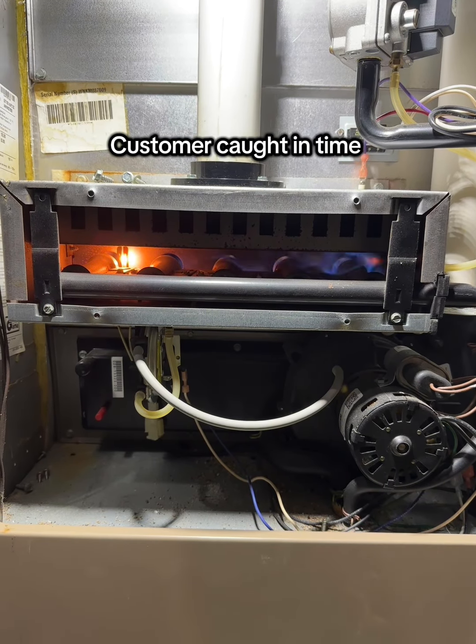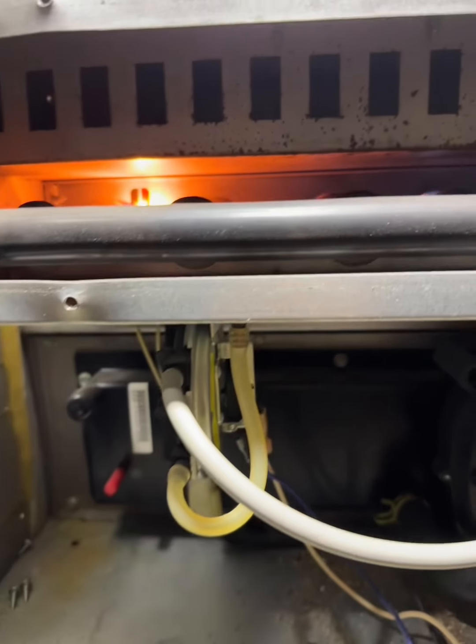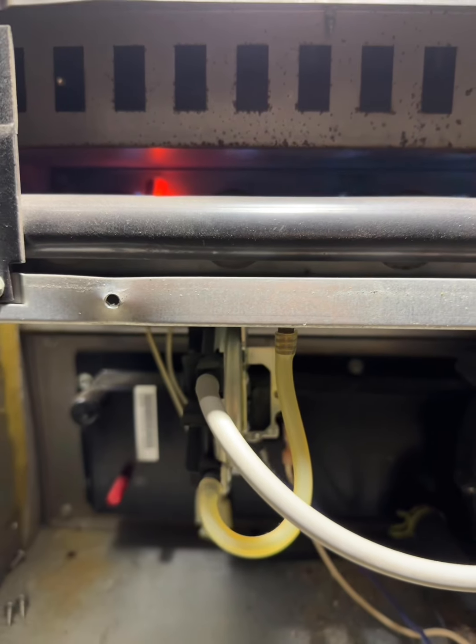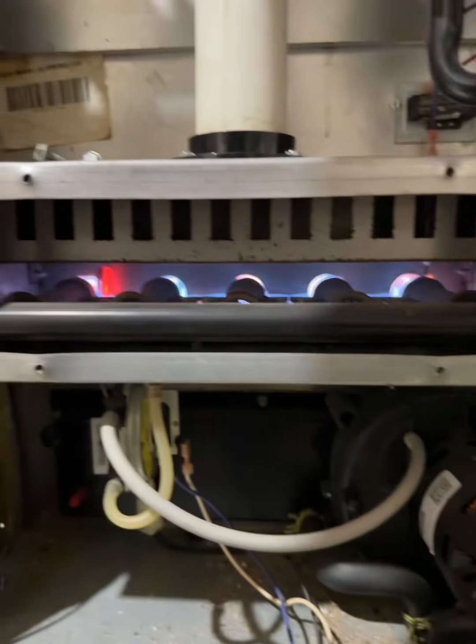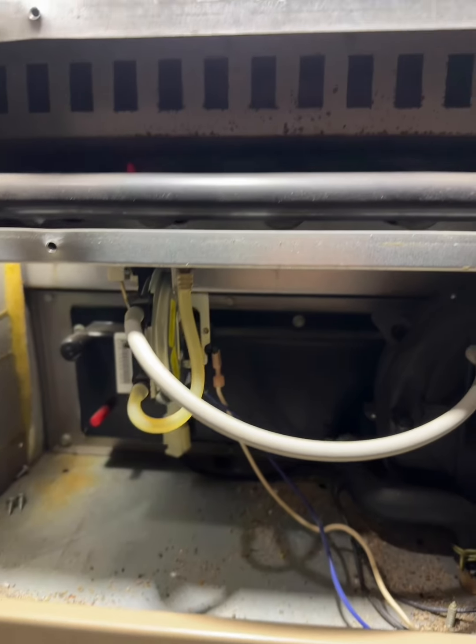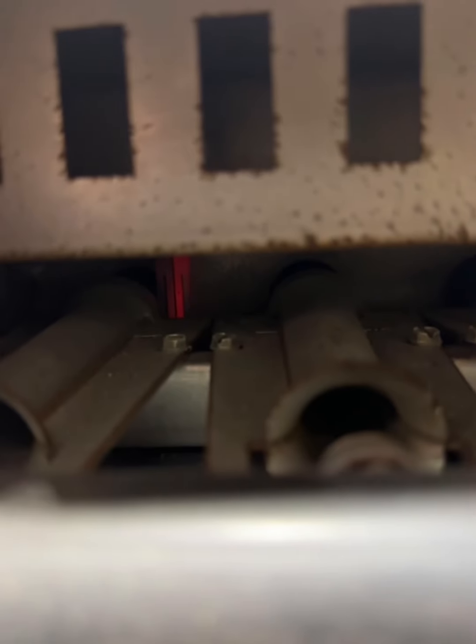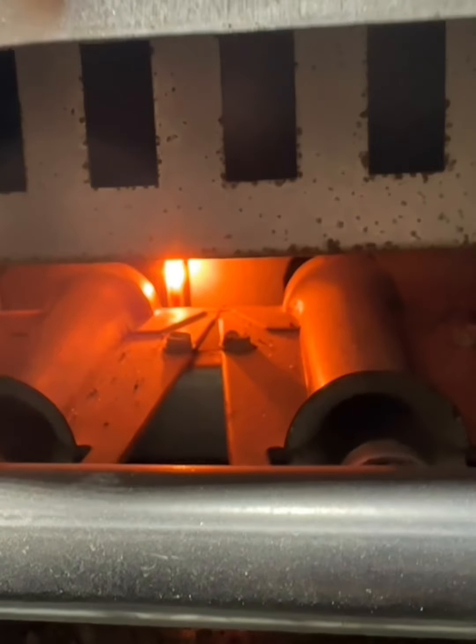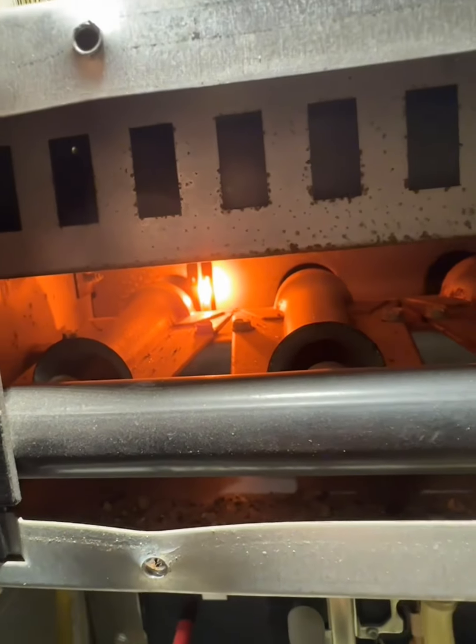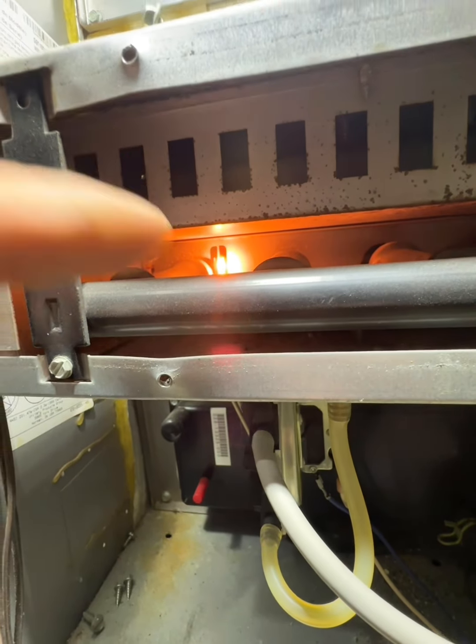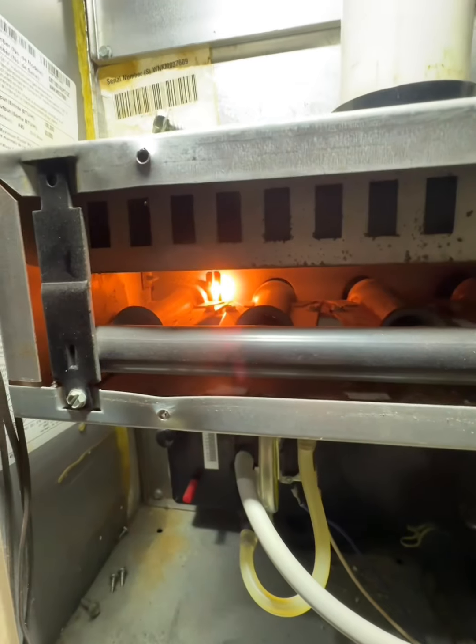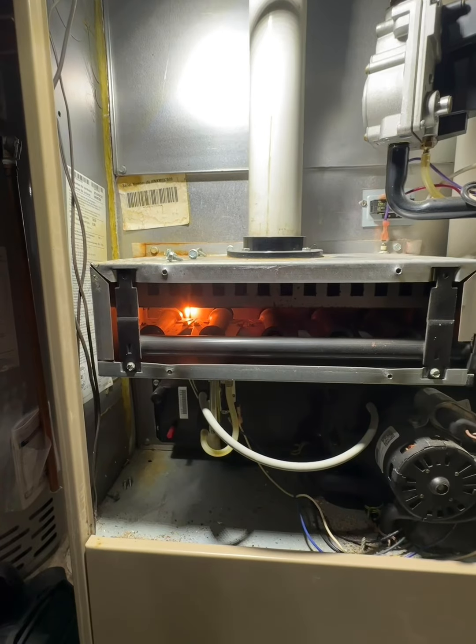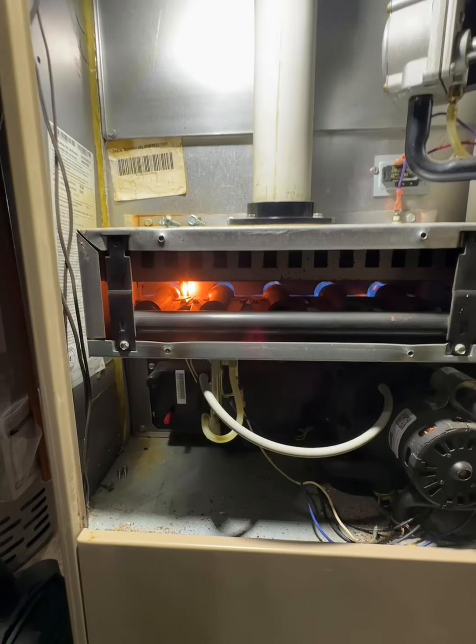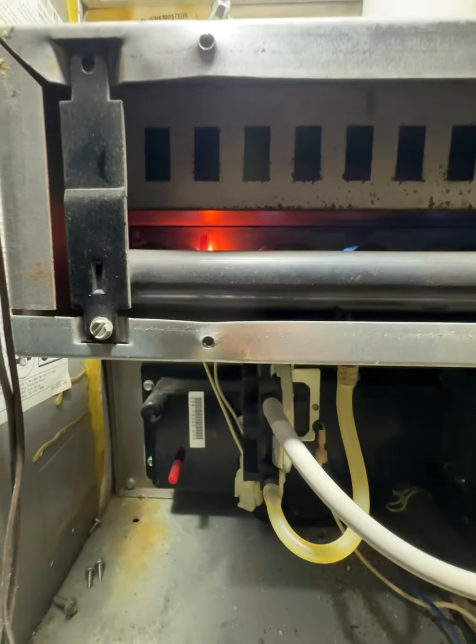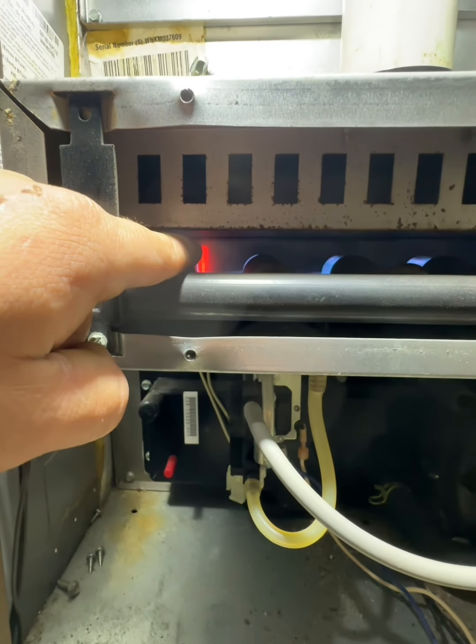Yeah, it looks like the igniter's not getting, well, the igniter's about to break. We're catching it right before it breaks. So this igniter doesn't get hot all the way. So then your gas is just kind of lingering in there, and then poof. Yeah, you see that? That's a hot spot on the igniter. That whole igniter should be lit up right now. So you can see it. Yeah, I kind of thought it was the ignition. That's crazy. Usually they break and they're done. So it still has a little bit of continuity through it. But yeah, you can see it where it's right there. See? Yeah, I see it.